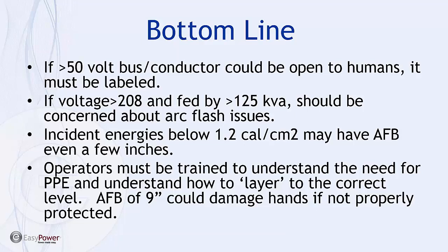This, to me, is less of a label issue and more of a training issue. If we have a training system that tells employees the NFPA requirement has changed, that this label currently indicates such and such, and what to use for PPE when they see a certain level of incident energy calculated—it may take a month or three months to change all the labels, but if there are questions, we should sit down and talk about the PPE level required, because it may differ from what's on the label.